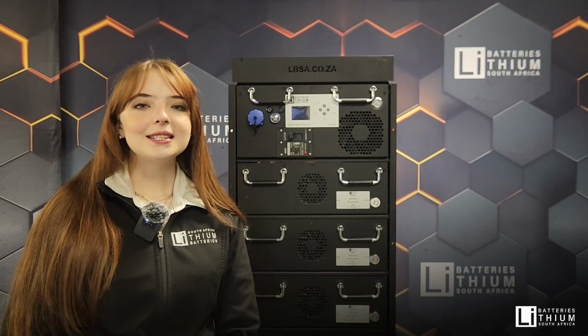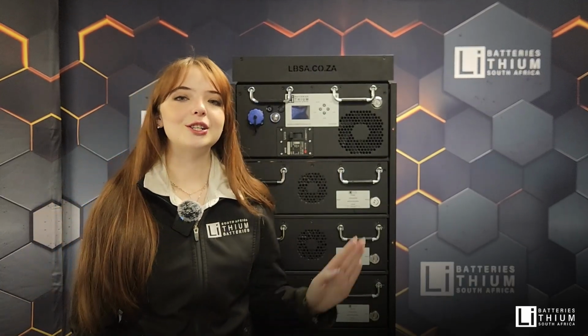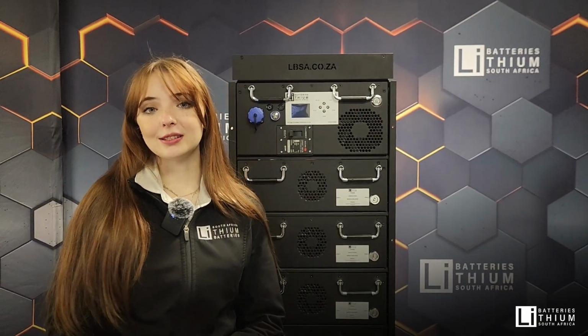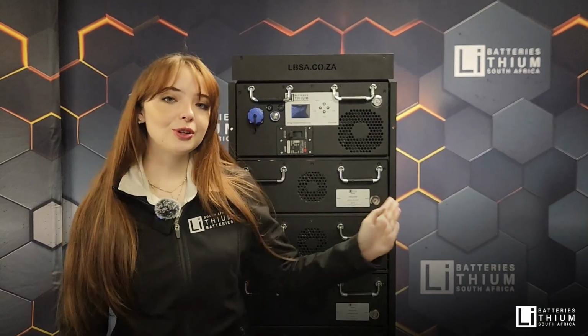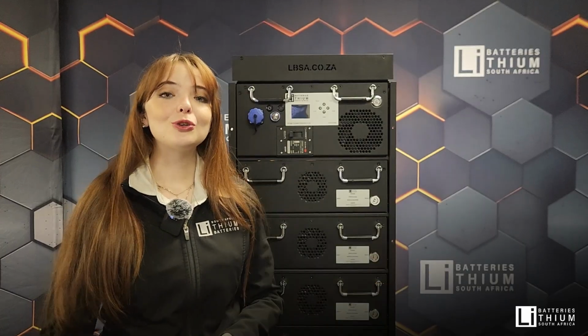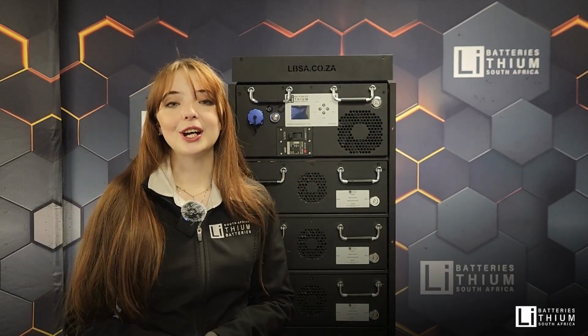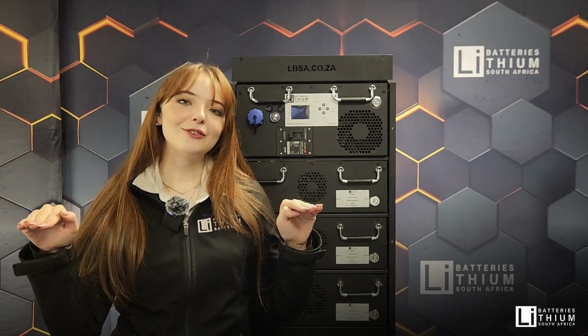The next thing I'd like to discuss is battery hot adding. When you are adding a new battery whose voltage is different from the rest of the installation, you don't have to worry about balancing. As soon as you add the new battery, it will either charge or discharge at 10 amps by using the bidirectional current limiter to balance itself out with the rest of the installation.